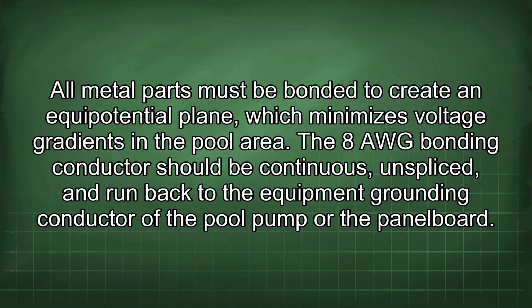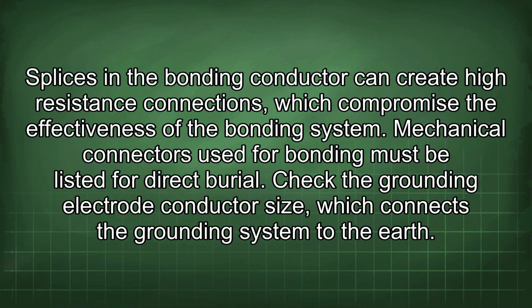The 8 AWG bonding conductor should be continuous, unspliced, and run back to the equipment grounding conductor of the pool pump or the panel board. Splices in the bonding conductor can create high resistance connections, which compromise the effectiveness of the bonding system. Mechanical connectors used for bonding must be listed for direct burial.